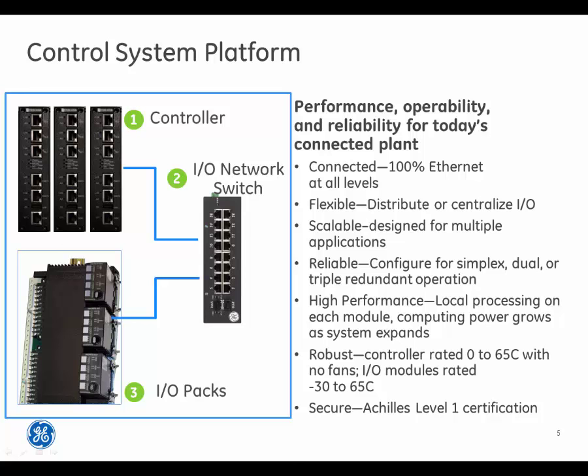It is a high performance system with local processing on each module, so computing power grows as the system expands. It is robust — the controller is rated from 0 to 65 degrees Celsius with no fans. I/O modules are rated from minus 30 to 65 degrees Celsius. And it is secure.